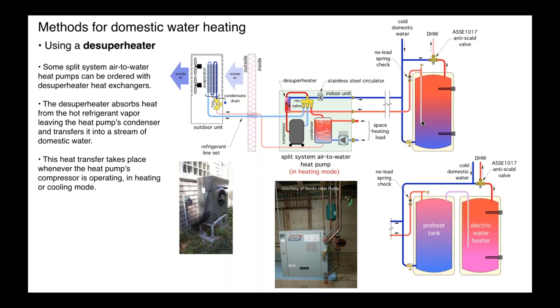Now, some air-to-water heat pump systems are available today with this. Nordic is one example. Here's the outdoor unit. Here's the indoor unit. The two larger pipes you see here are the main output of the heat pump going to space heating. The refrigerant line set connects here on these service valves, that hasn't been installed yet, but you'll see a couple small pipes up here. Those are probably either half inch, maybe 3/4 inch tubes that go off to the domestic water. That's a de-superheater.